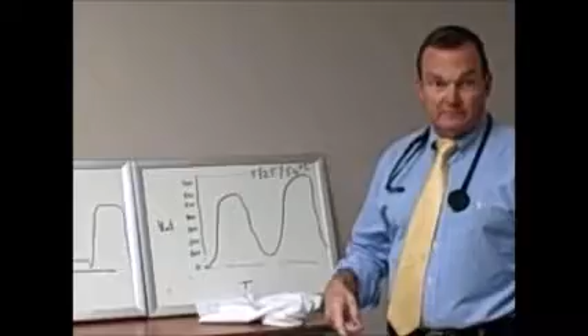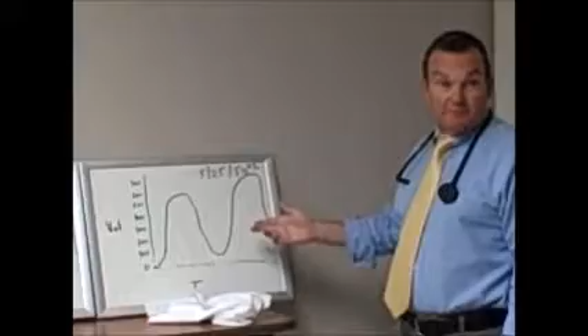Do you know how pressure support's terminated? When the demand valve opens, it gives him that pressure, CPAP plus pressure support, because there's no PEEP, and it holds that pressure until his inspiratory flow rate decreases by 75%. So they call it the peak flow 100/25. When his demand decreases to 25% of what it initially was, then the pressure support is turned off. Okay? So if we had a longer tracing, the volume may well change on CPAP pressure support, but the pressure won't. Okay?